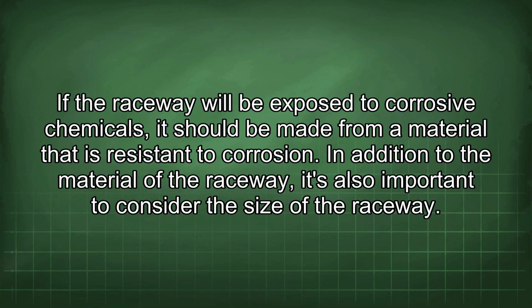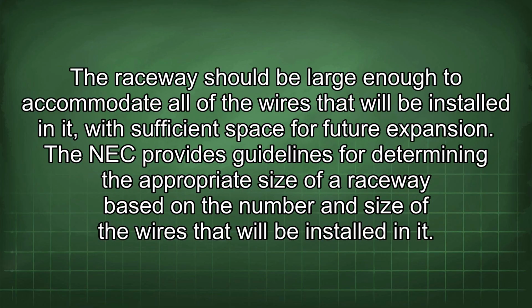In addition to the material of the raceway, it's also important to consider the size of the raceway. The raceway should be large enough to accommodate all of the wires that will be installed in it, with sufficient space for future expansion. The NEC provides guidelines for determining the appropriate size of a raceway based on the number and size of the wires that will be installed in it.